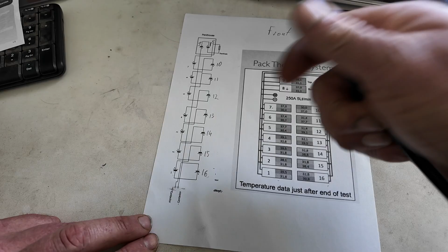The negative contactor is connected to the negative side of module 16, the last one in the chain, and then it winds over to module number 1. This is a series connection, so each module is in a chain. Plus is connected to minus, and this plus is connected to minus of number 15. So number 1 winds over to 15, positive of 15 winds over to number 2 on the negative, and so on. That's how it zigzags its way forward to the penthouse.